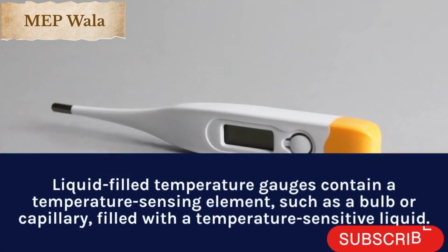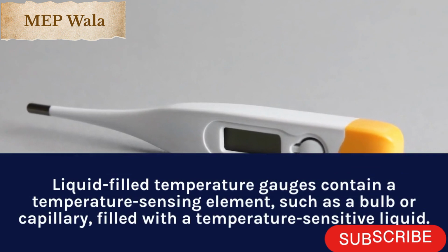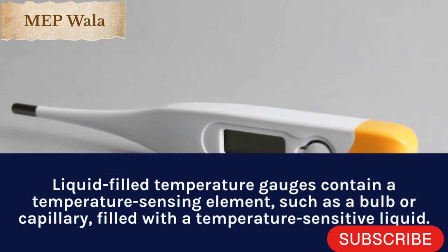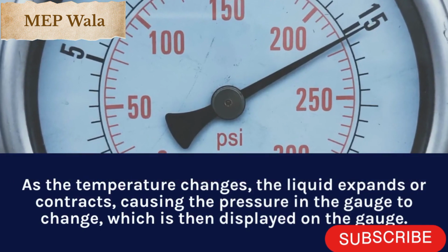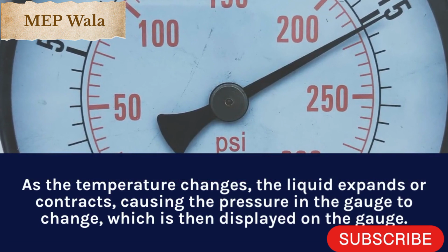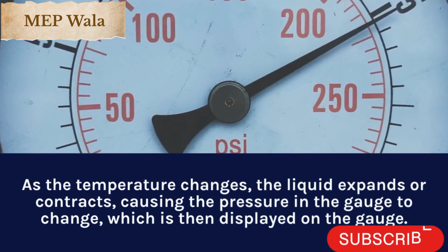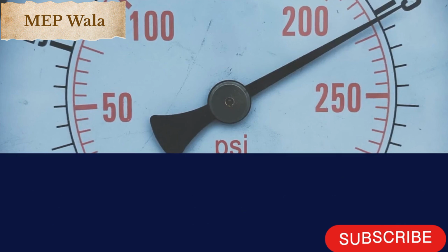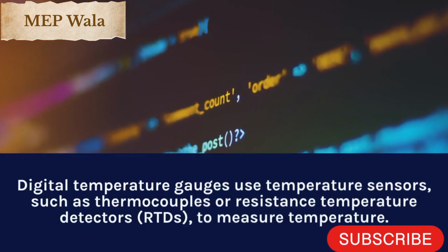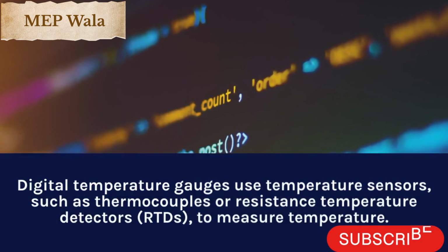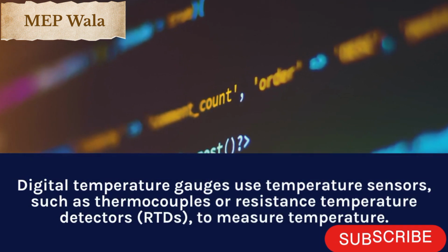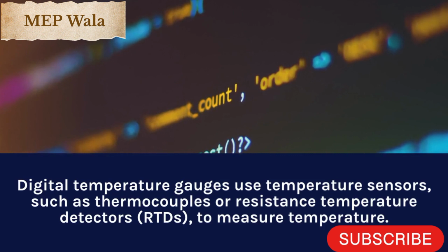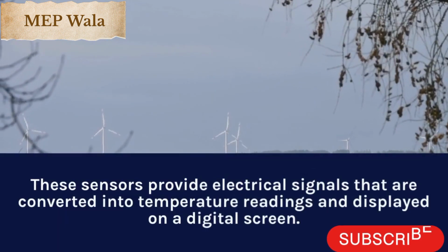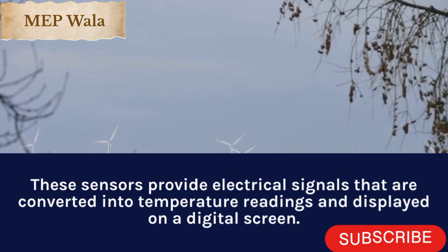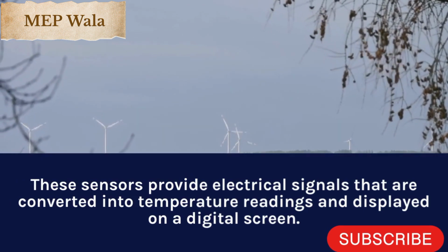Liquid-filled temperature gauges contain a temperature sensing element, such as a bulb or capillary, filled with a temperature-sensitive liquid. As the temperature changes, the liquid expands or contracts, causing the pressure in the gauge to change, which is then displayed on the gauge. Digital temperature gauges use temperature sensors, such as thermocouples or resistance temperature detectors, RTDs, to measure temperature. These sensors provide electrical signals that are converted into temperature readings and displayed on a digital screen.